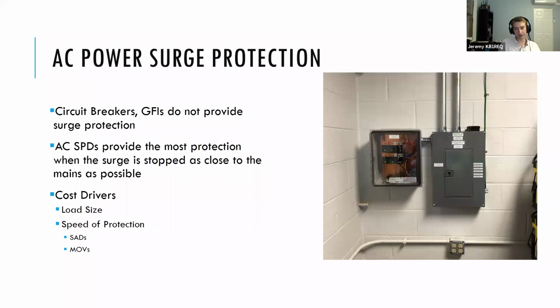So AC surge protectors, like our RF surge protectors, have a threshold voltage, and they shunt your electrical connections to ground when that's reached. An AC surge protector, just like RF surge protection, is most effective when it's as close to the input as possible, keeping the surge away from your devices as much as possible. So the best method, obviously, is to surge protect right at the panel, right when those mains come in. That, consequently, is going to be your most expensive as well, because that device has to be built for the entire load. If you've got 200 amp service, all of the devices in there have to, under normal circumstances, carry 200 amps.